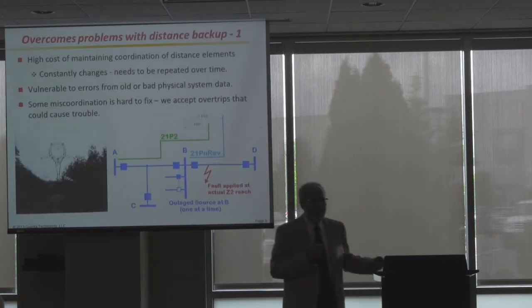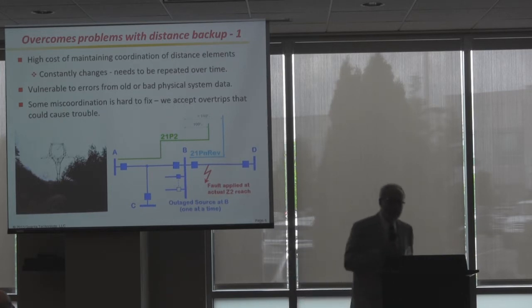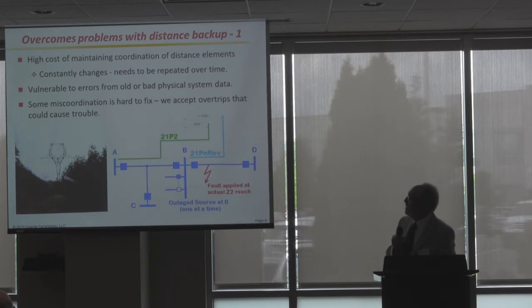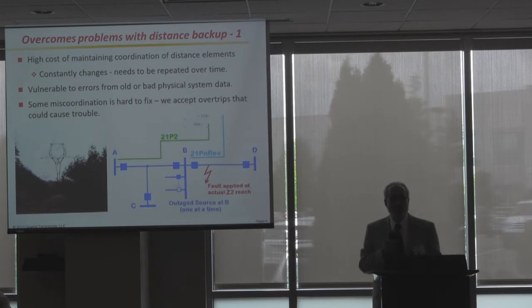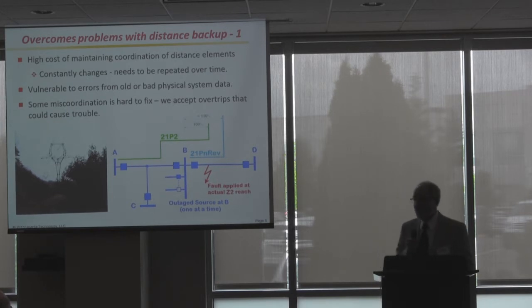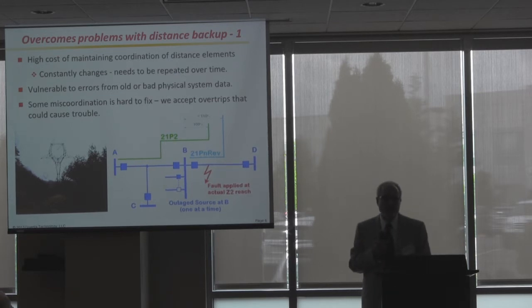Why do we want to try something that's quite different from what we're familiar with and that we feel comfortable with? Well, the schemes that we have today using zone 2 and zone 3 relays have massive coordination challenges. I can tell you that a lot of my colleagues and I actually have a lot of work that we do helping utilities review their coordination. It's a giant job, a huge project to go through and see if these relays are set correctly. And you have to do it all the time because the systems are evolving, fault current contributions are changing, and you can lose coordination. If you don't have really good physical data on exactly what the transmission line or the other apparatus looks like, what impedances are and so forth, you're going to get errors from that. And then you find miscoordinations and you can't even fix them. You just have to make a bad choice and do something. So these are all problems with these existing methods.